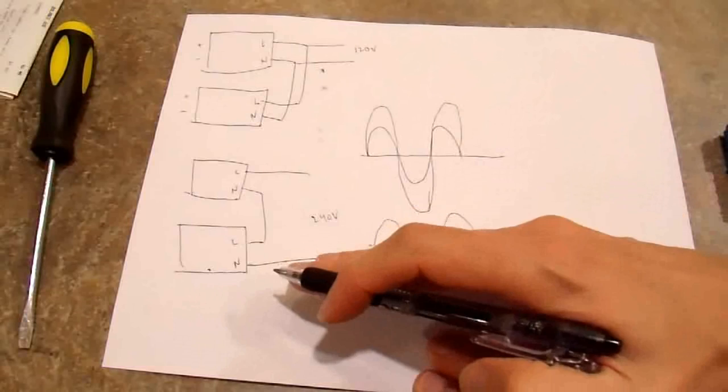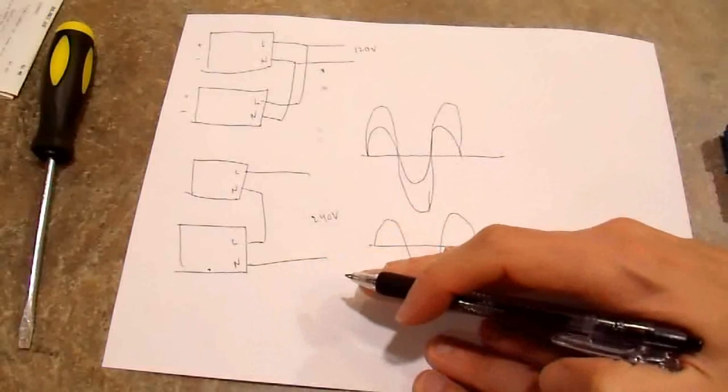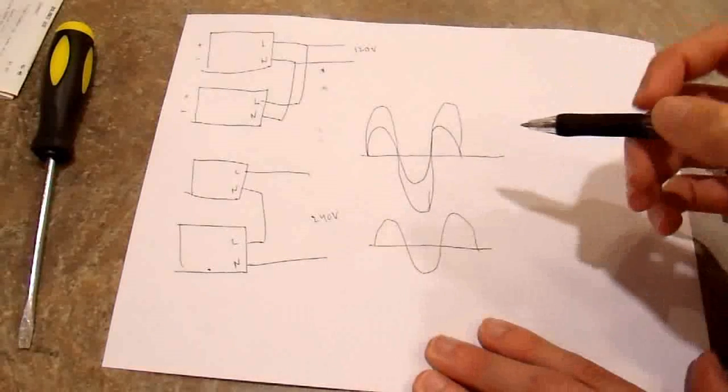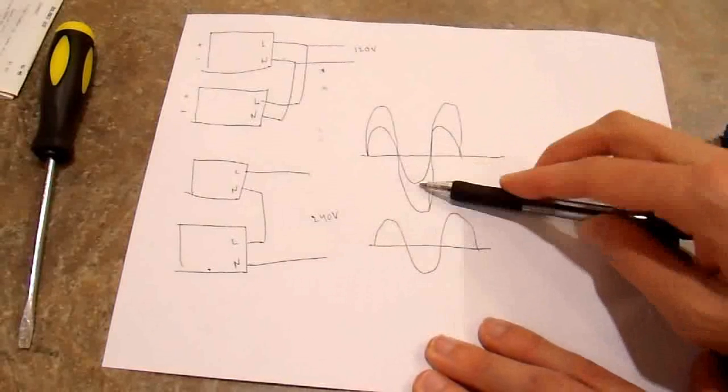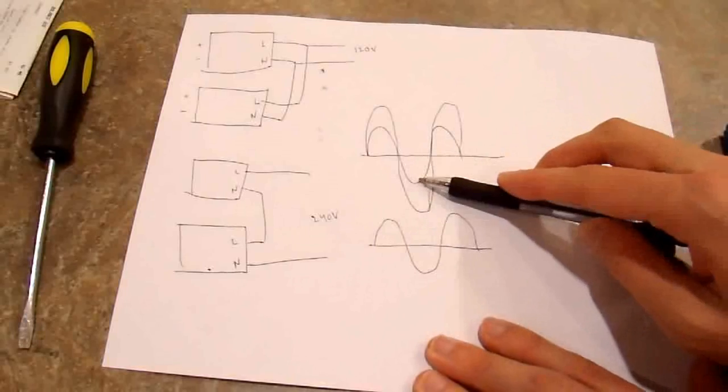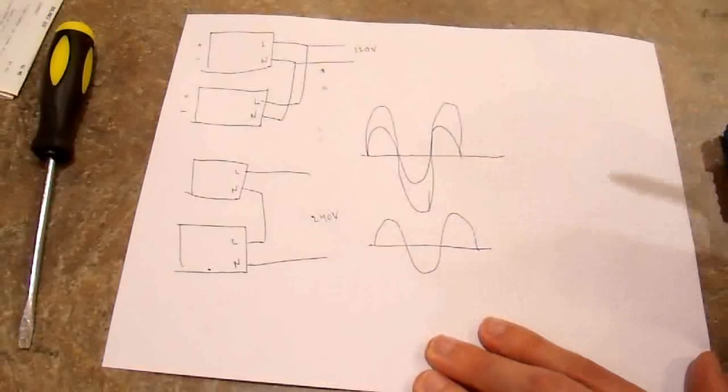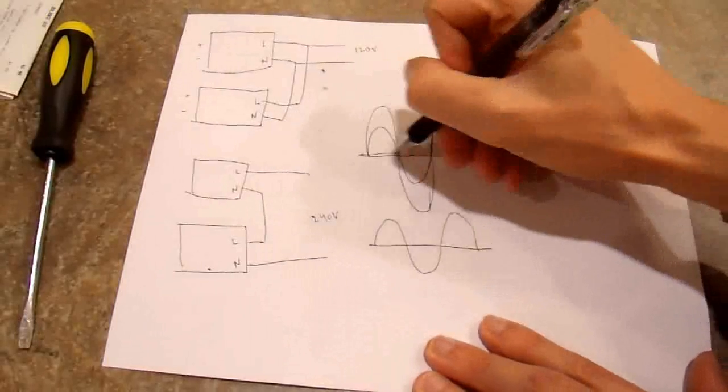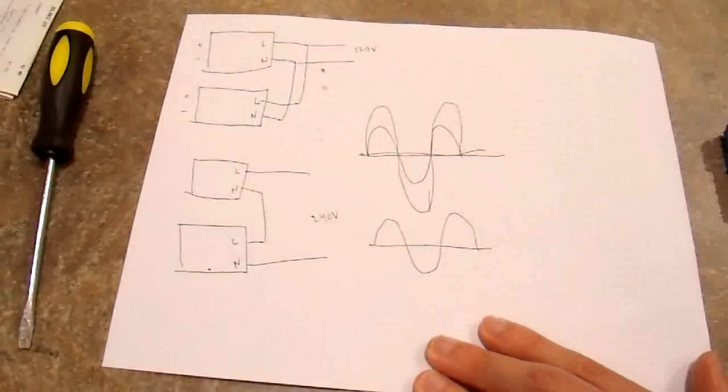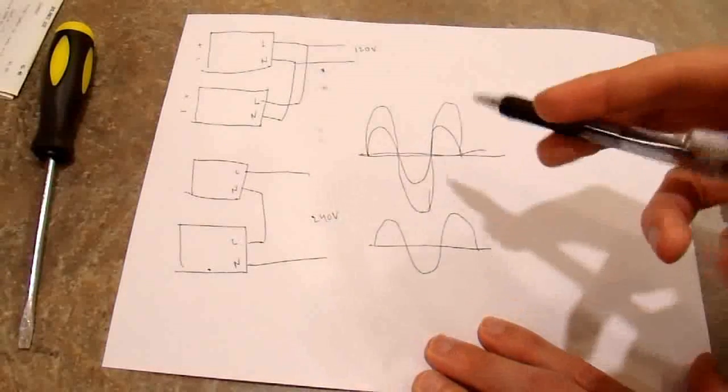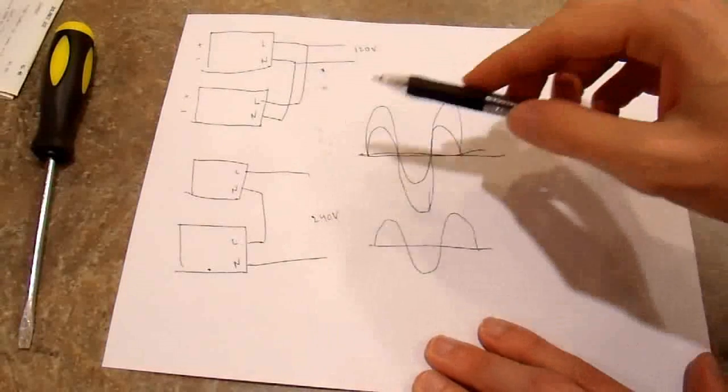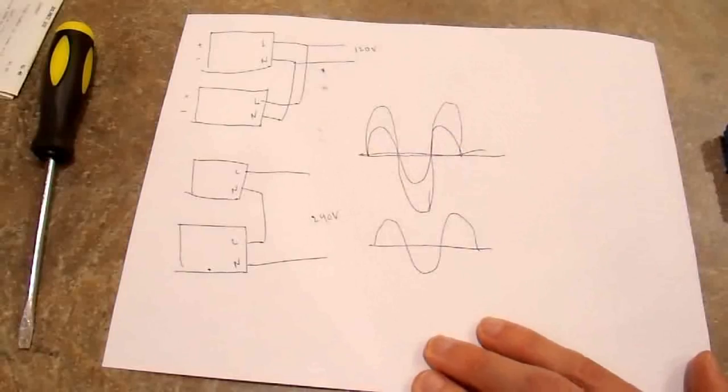If these were shifted and they weren't perfectly in phase, then this peak would correspond to this trough, this trough would correspond to this peak, and you'd end up canceling out and you'd end up with 0 voltage. And that's why it slowly oscillates between 240 and 0 if they're not perfectly synchronized.